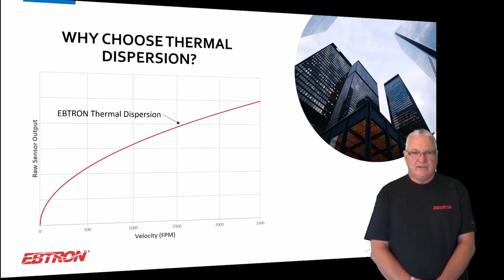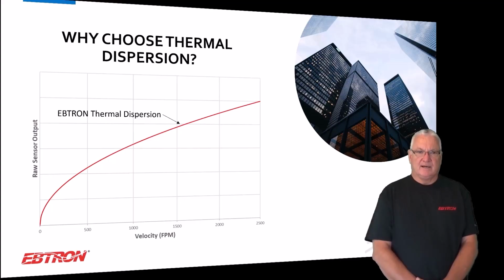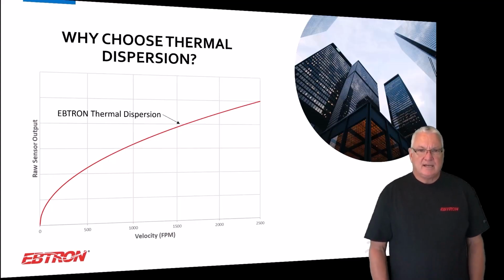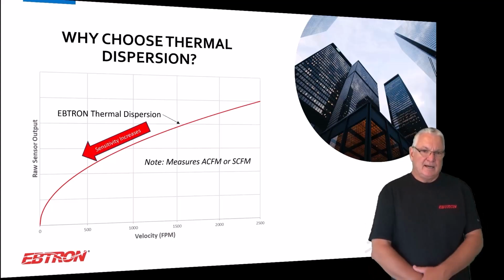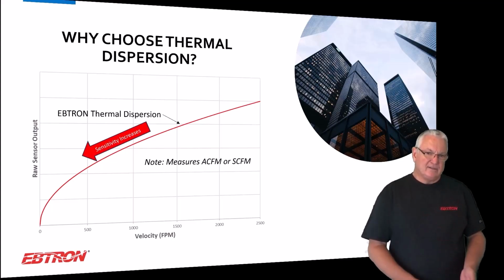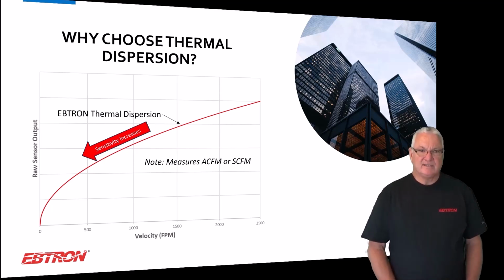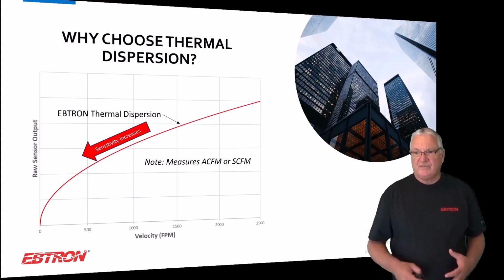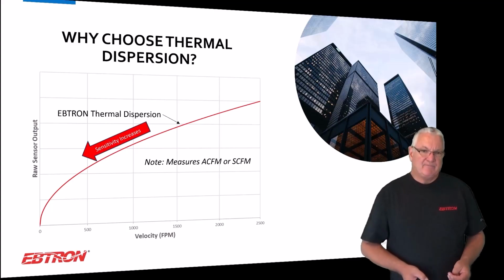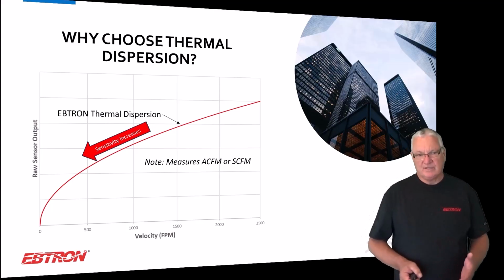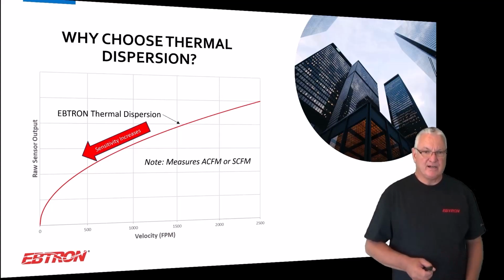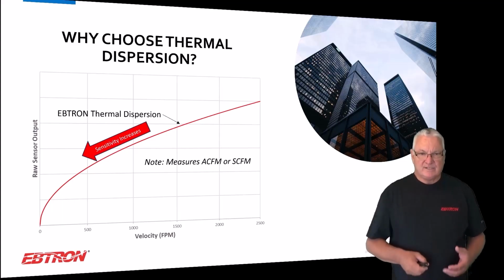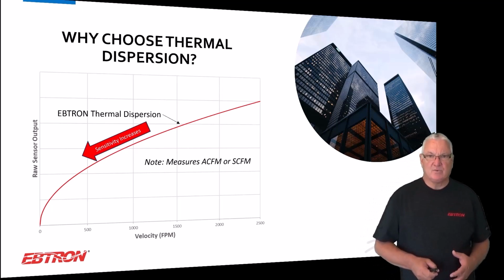All right. Well, one reason to use EBTRON thermal dispersion is we've been doing it for 40 years, but really the technology itself is ideal for HVAC because as the airflow rate goes down, the sensitivity increases, and that's really good because most, if not all, of our HVAC applications are relatively low velocities. There's a few that are really high. Fan inlet measurement is right on the border. What I would say is we're starting to get high, but we definitely can measure there. But when you get down to things like supply and return airflow rates in ducts or outside air intakes, those flow rates are pretty low. So having a device that is most sensitive at the low flows is really great.